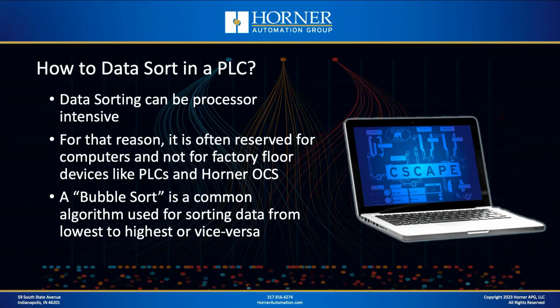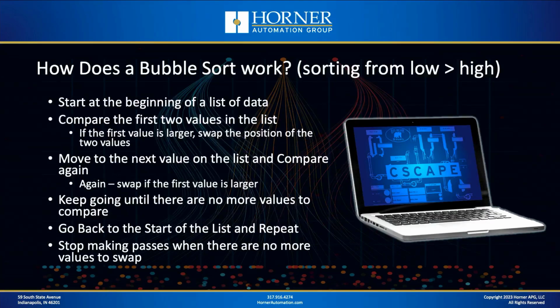Okay, but let's now talk about data sorting in a PLC. The reason it's not done that often in a PLC is because it can be processor intensive. For that reason, you often find the sorting done on computers, offloading the PLC. However, we're going to show you today how you can do it quite easily and quite safely in the Horner OCS. We're going to use something called a bubble sort algorithm, applied in a user-defined function block, so that you can just use that UDFB as we've written it to make sorting data nice and easy.